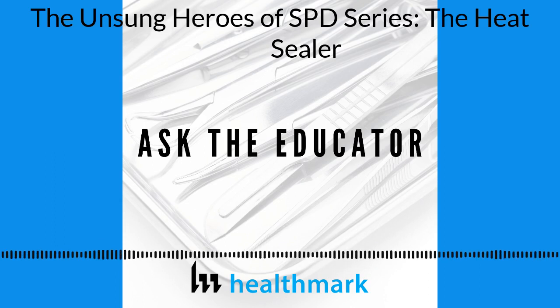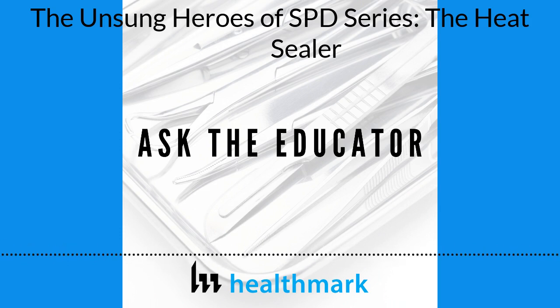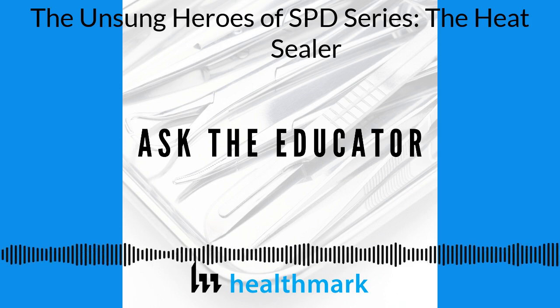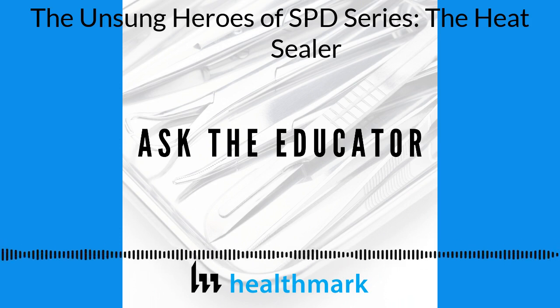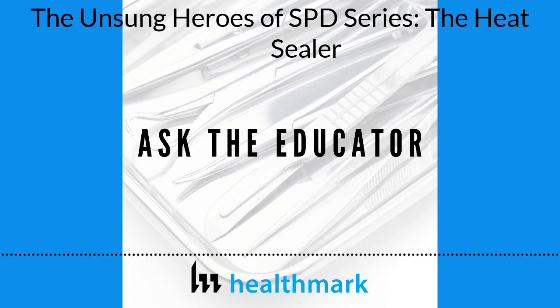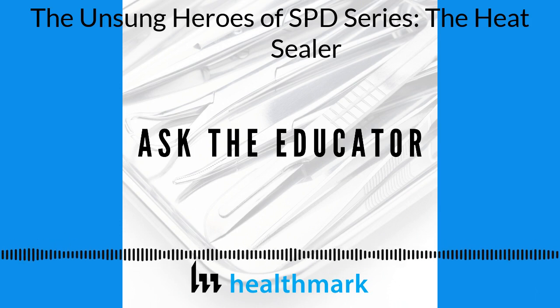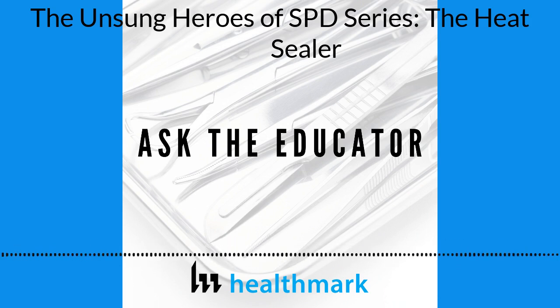If you look in AAMI ST79, they have a section on packaging and making sure integrity is there. If you look at ST90, it says you should put in programs for the equipment you have. And then we have a document, TIR 22, which deals with peel pouches and sterile barriers and so on. That also dovetails into the ISO document 11607, which is what they use in Europe and everywhere else. And they do daily testing. And then within there, you have ASTM standards, which talk about a dye test. So there is enough information and guidelines to help you do it.